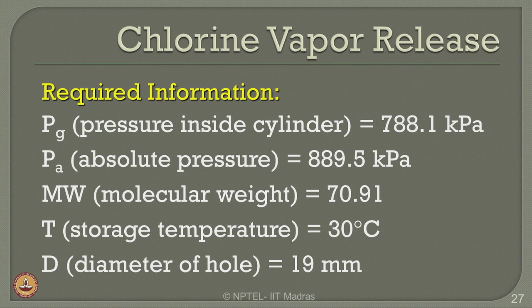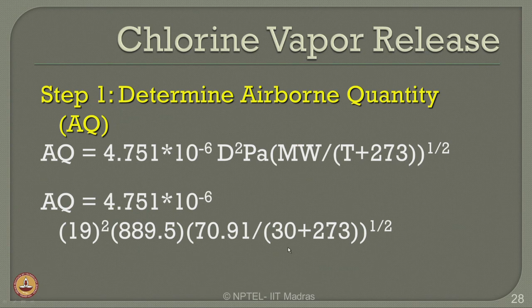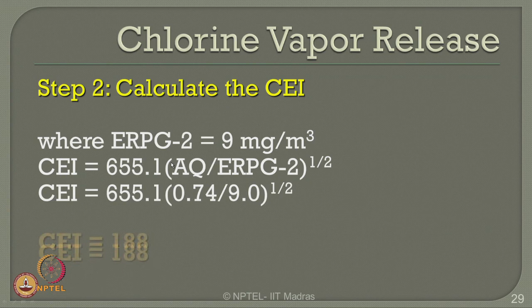Step 1, determine the airborne quantity of this chlorine vapor given by this equation. I know the values, substitute them, converting temperature into kelvins by adding 273, and get the airborne quantity as 0.74 kg per second. Now I want to compute directly the CEI. The ERPG level 2 for chlorine vapor is 9 milligram per cubic meter. I substitute the value, I get CEI as 188. Then I compute hazard distance for ERPG 2. I get hazard distance as 1.878 kilometers for ERPG 2.